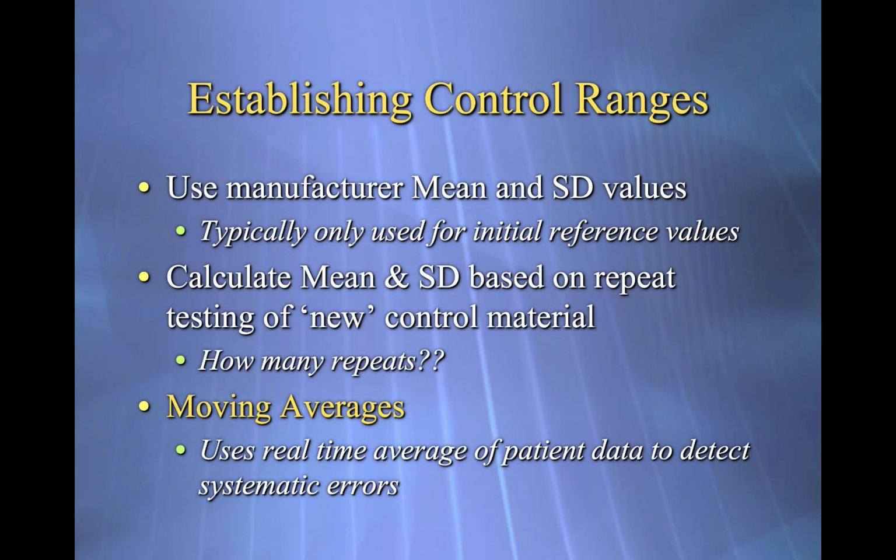Okay, I'm going to get some new controls out before I run out, and I'm going to run those controls in parallel. It's a great way to do it. Say 10 times. If you could do it over 10 samples over a couple of shifts or a couple of days, and then compare that data, and you say, well, the old controls are still in control, that means I'm in control, and here are the values for the new control. Then I can calculate a new mean and standard deviation based on the new control material data.